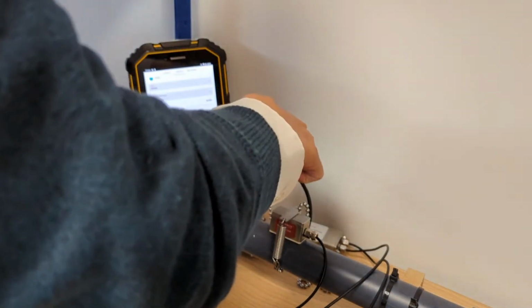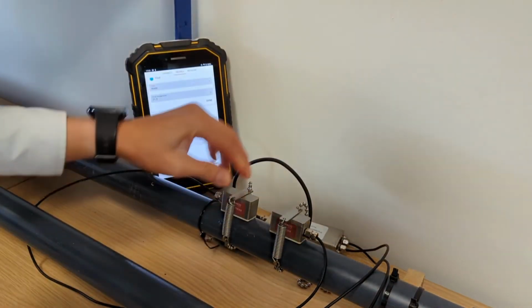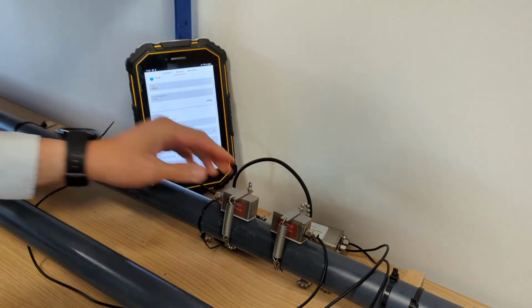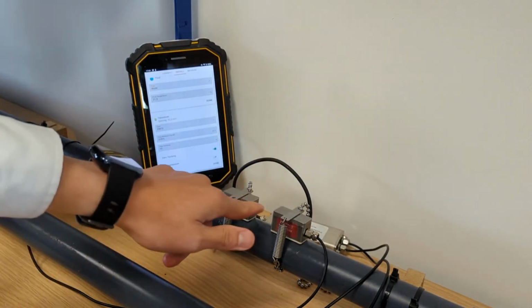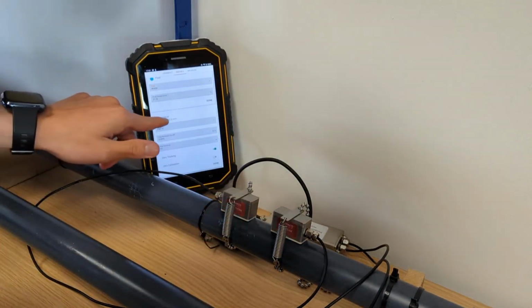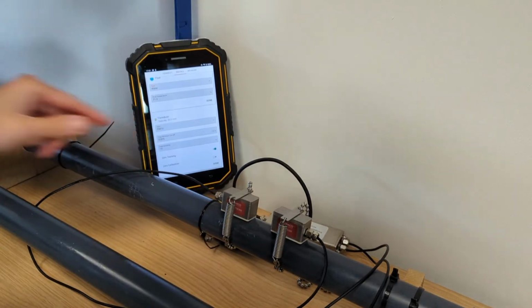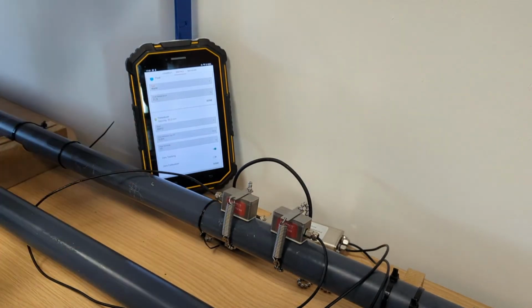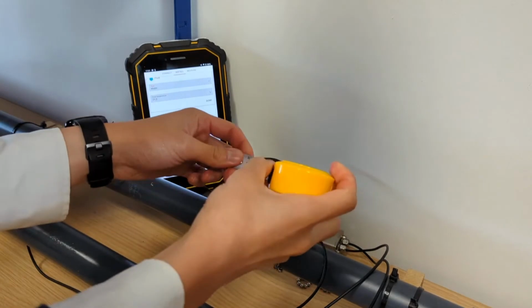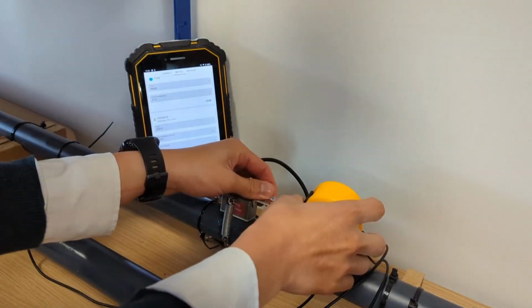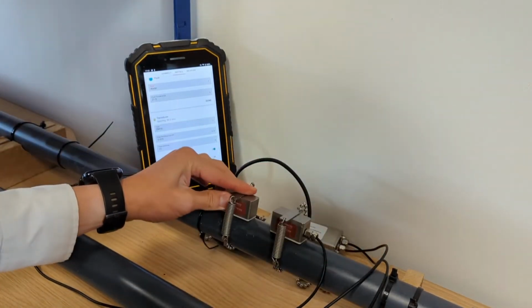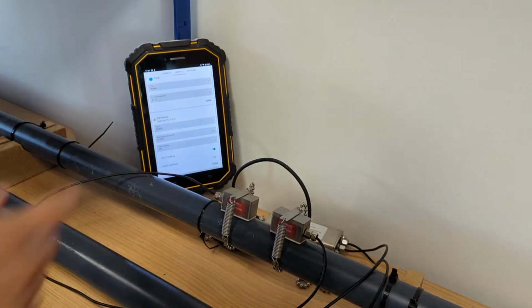Ensure the sensors are securely fastened and then measure the distance between the sensors. Reference the transducer spacing, which is 30.3 millimeters. I'm measuring this now, and it is 30.3 millimeters. Once you have the right spacing, press Measure.